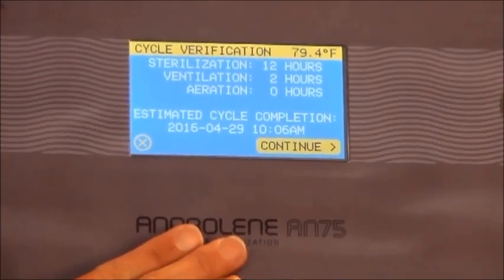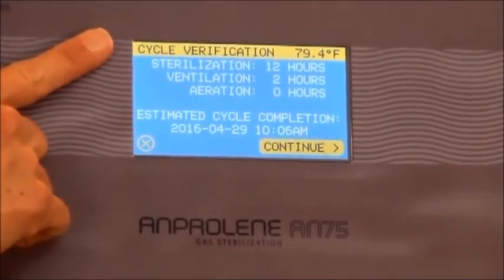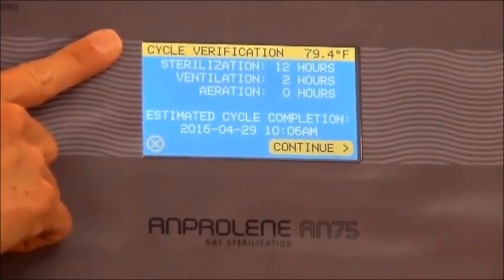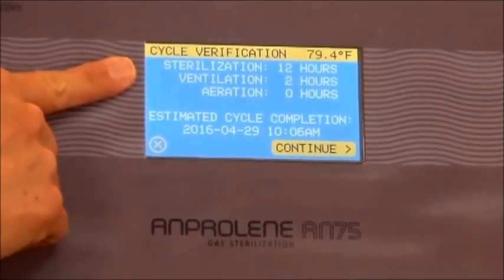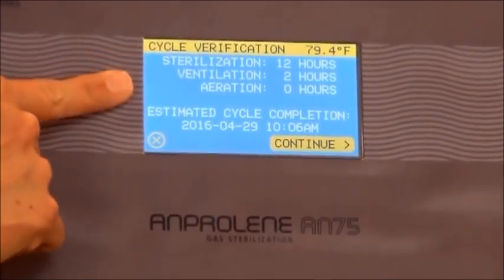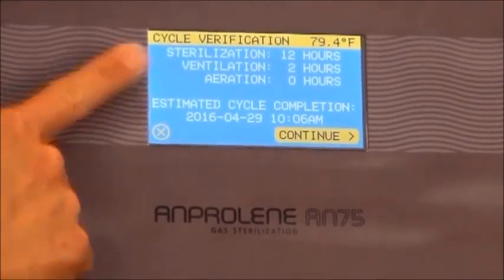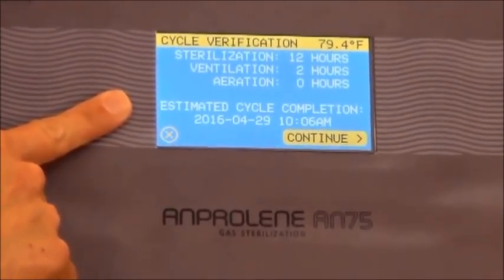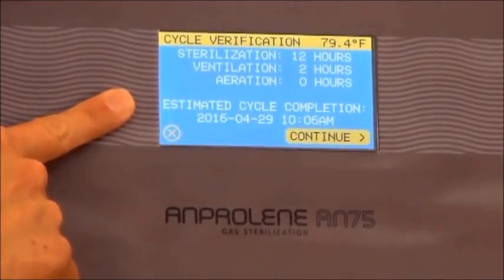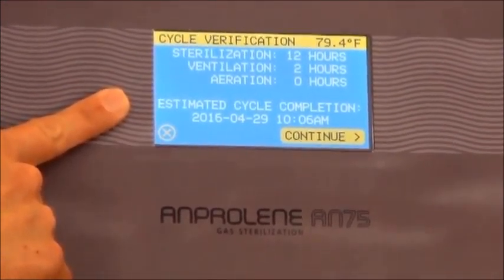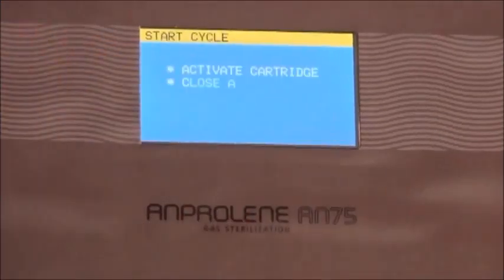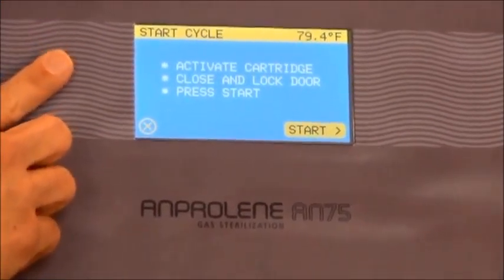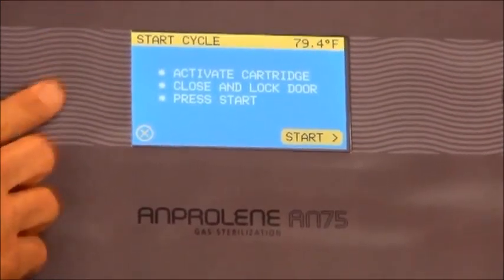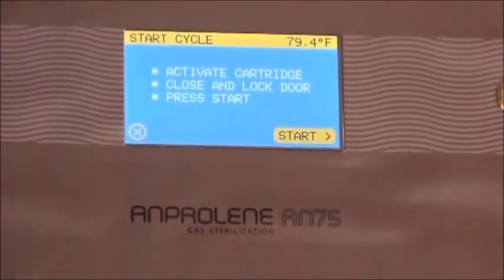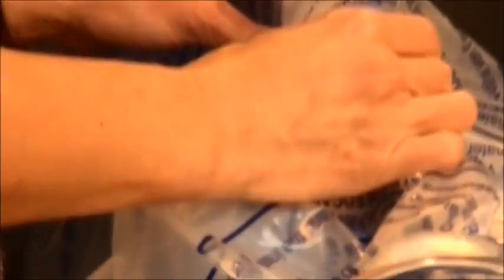Your cycle verification screen will show you the length of the sterilization cycle, which is 12 hours, ventilation, which is an additional 2, and any aeration time that has been selected. Finally, it will give you an estimated time of completion, so you will know when your cycle has been finished. At this point, you can press continue, follow the instructions on the screen, activate your cartridge through the liner bag by pressing on the blue trigger.